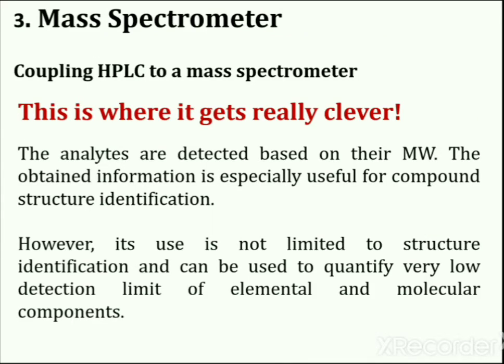The third detection method involves coupling the HPLC system to a mass spectrometer. When the detector is showing a peak, some of what is passing through can be diverted to a mass spectrometer, where it will give a fragmentation pattern that can be compared against a computer database of known patterns. This means the identity of a huge range of compounds can be found without having to know their retention times. Analytes are detected based on their molecular weight, and the information obtained is especially useful for compound structure identification.